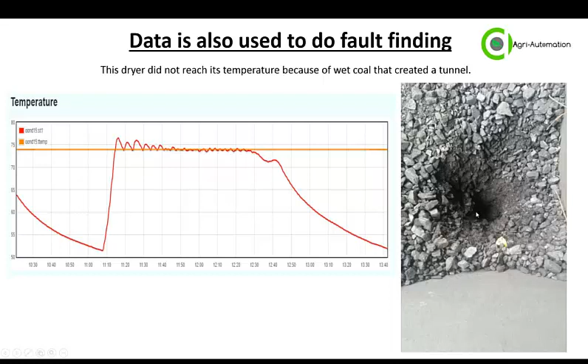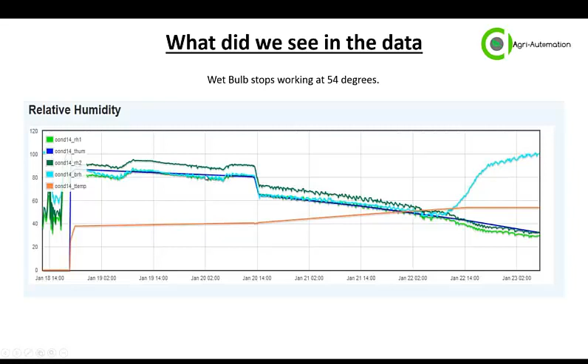exchanger. We found that wet bulb stops working at 54 degrees, so controllers that work with wet bulb will not work past 54 degrees, and that's why here we had a wet bulb probe in there, just to see. Our relative humidity probes still kept going fine, but at this point the wet bulb would break away and basically became the same temperature as the dry bulb.